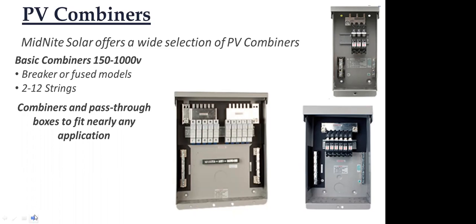What I mean by that is we're probably the most guilty party, but we have a combiner box we call the MNPV6. So you would look at that and say 6 strings, right? And it is if you use breakers, like you see down the bottom right corner there. But if you use fuse holders, it won't hold 6; it only holds 5. So you have to look at the specs on the box, I guess is what I'm saying.